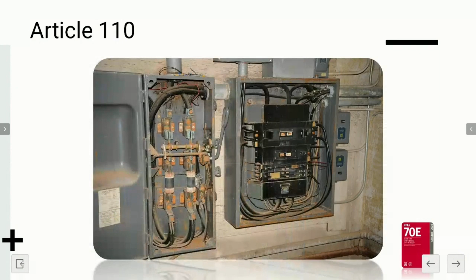Took the cover off a transformer, there's a squirrel between the phases of the transformer, just fried. So we need to look at documentation. If it wasn't documented, they probably didn't maintain it. It hasn't been maintained unless for some reason they can prove to you that they have. Because 90% of the people don't know they need to maintain it, and they don't maintain it. So you can almost guarantee it hasn't been maintained.